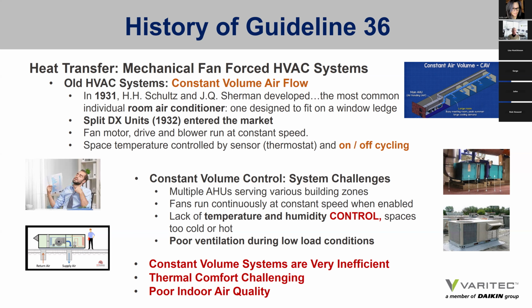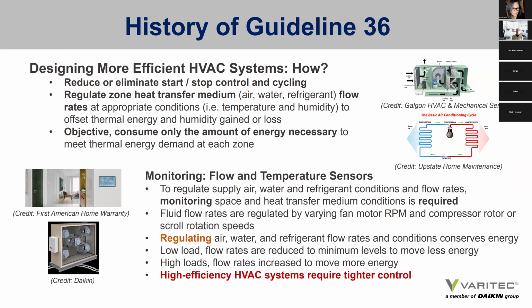To effectively condition a building with various loads at various times of day at various parts of a building, you required a number of different air handlers to make sure each area or group of zones were adequately conditioned. Fans ran continuously at constant speed, so there was a lack of temperature and humidity control, and often poor ventilation, certainly when thermostats were met and units were shut off. So constant volume systems are very inefficient. You get what you get when they're on, and you don't get anything when they're off, which provides thermal comfort challenges and poor indoor air quality.